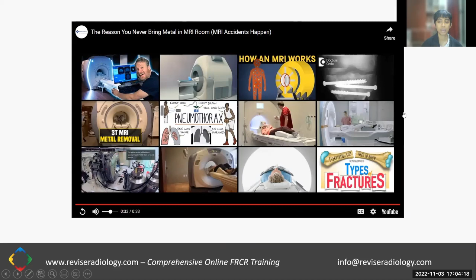What kinds of incidents can occur when metal is brought near the MRI magnet? There's the ferromagnetic missile effect on metal outside the patient's body. There might be migration or rotation of metal implants or fragments within the body itself. There may be current induction and heating of metal outside the patient's body and in implanted devices. There are three magnetic fields which, as we'll see during the webinar, can cause these kinds of incidents to occur.